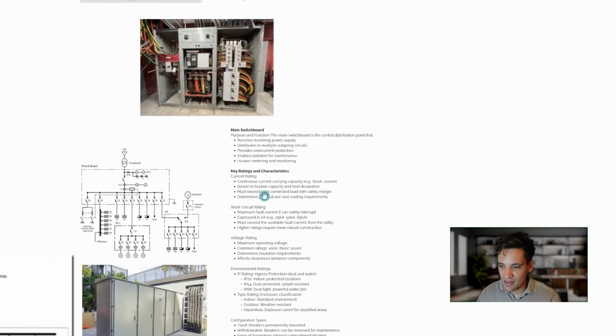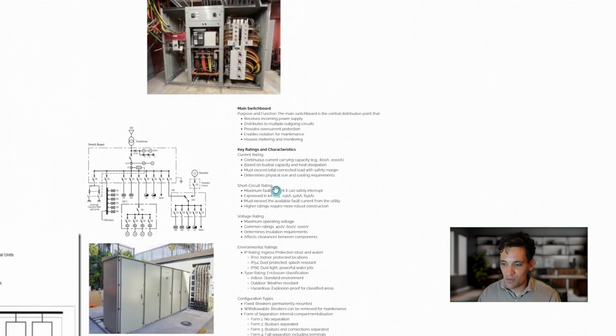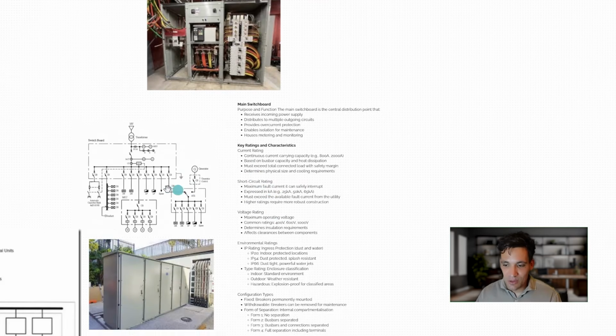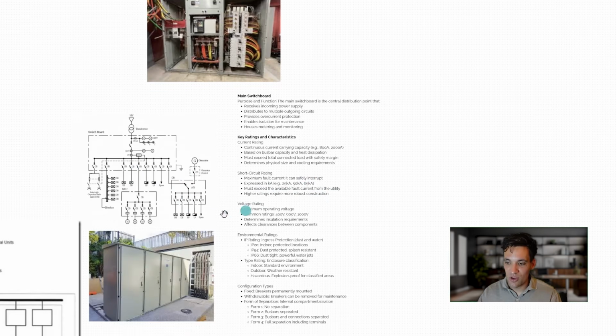When we talk about a main switchboard, we generally rate them based on their current rating. So what is the typical continuous incoming current that they can take? It might be 800 amps or 2000 amps, which is going to be based on the bus bar capacity and how it distributes heat. If you have a small bus bar, you can't continually take 2000 amps because it'll lose a huge amount of power through the I squared R power losses. The bus bar capacity needs to exceed the value of the total connected loads by a margin, and it determines the physical size of the main switchboard.